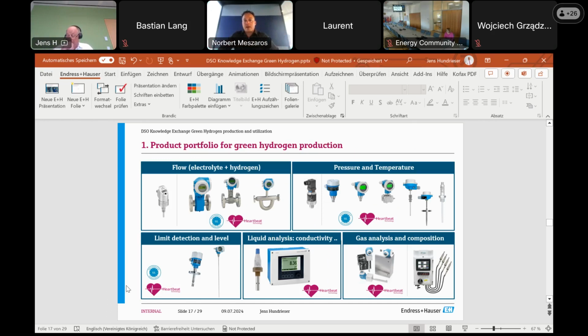Considering pressure and temperature devices, you can right now use gold-coated pressure devices and be hydrogen ready. But considering flow measurement devices, it's not so easy, because for delivering the same energy, you may face 2 to 3 times higher flow velocity, and it would decrease the flow dynamics measuring ranges drastically.